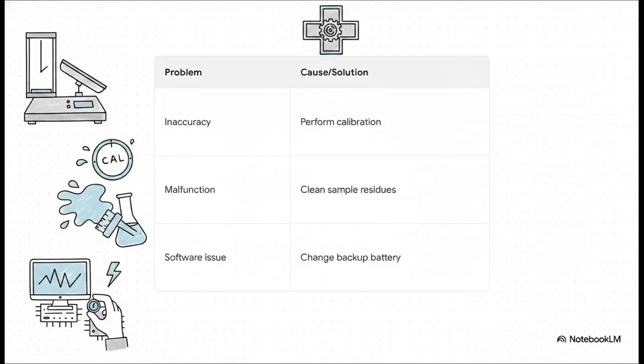So if a balance starts acting up or throwing erratic readings, it really highlights how delicate this hidden engineering is. It could be something as simple as a few drops of spilled liquid messing with a weighing plate. More seriously, if someone overloads the balance, it can permanently bend the super delicate internal load cell, which basically ruins the machine. Or, hey, if the software is glitching out, you might just need to swap out the dead backup battery for the internal microprocessor.